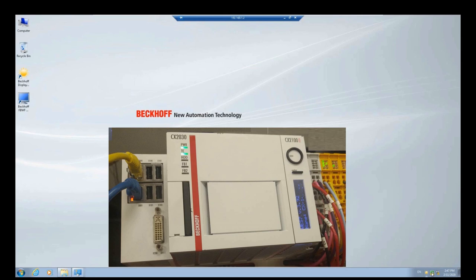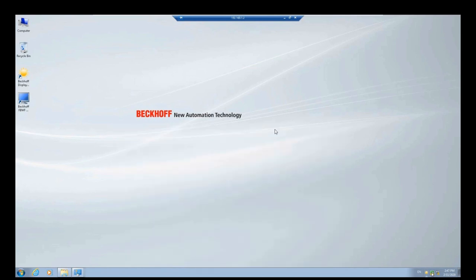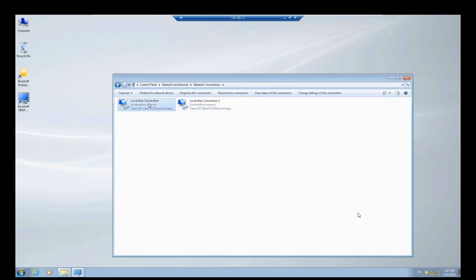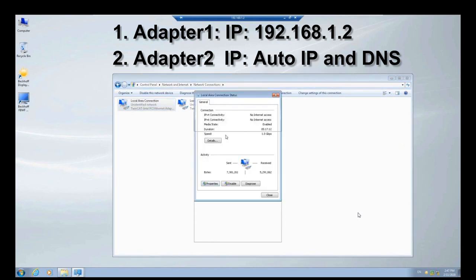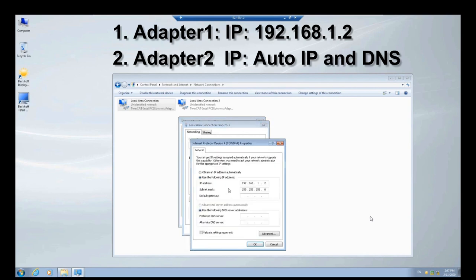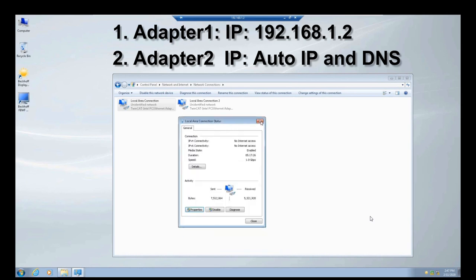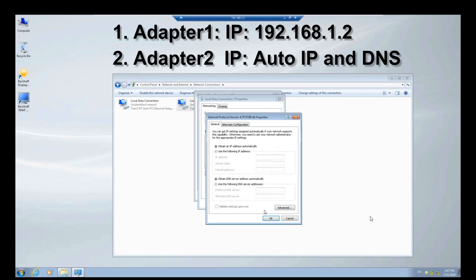When you turn on the CX controller and the system logs in, you can use the administrator account with the default password, which is '1'. When you log in, it shows the Windows desktop on screen. We can go to the network adapter connections. The first adapter is set with a fixed IP — that is 192.168.1.2. The second adapter in this controller is set to dynamic, or automatic IP address.